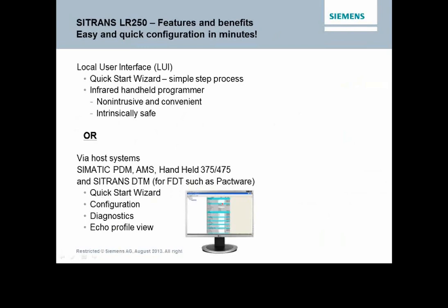The advantage that you get when you use the software, and it's inexpensive, I think it's under $100, is that you have the visibility to all the parameters simultaneously. You can save parameters. Our service guys use this tool quite a bit when they're out in the field because they can pull up a device, grab all the parameters, review parameters, save parameters, and do as found, as left records, as well as diagnostics and complete echo profiles. So it's nice to be able to take a look when it comes to setting up an actual tank or process, and being able to review the application parameter by parameter and make adjustments by those parameters.